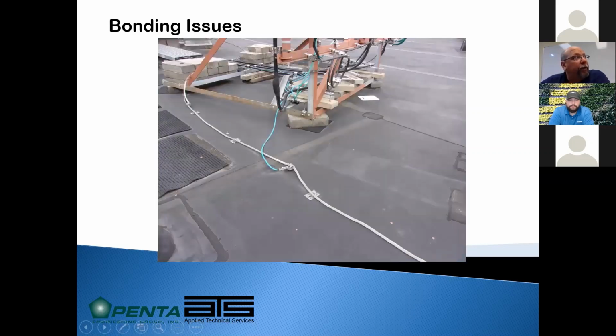We have a lot of communications equipment. More and more cell phone providers are renting rooftop space and putting up antenna sleds. The lightning protection should be an independent grounding system. Communications equipment should be using the building's grounding system, the electrical grounding for the building, as their grounding. We should have a bonding connection to make sure we don't get potential energy differences between the equipment. But satellite dishes, antenna cell towers, they see this lightning protection conductor, they know it's a great ground, and this prevents them from having to run another 100 feet of cable to get to the building. So many times they just attach it directly to the lightning protection. That is not approved by UL for lightning protection systems. It's an undersized bond. It's not approved to carry the energy. And it could also backfeed into the actual equipment and make that equipment go down.